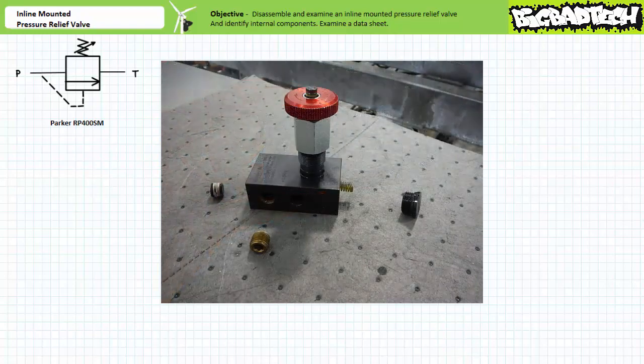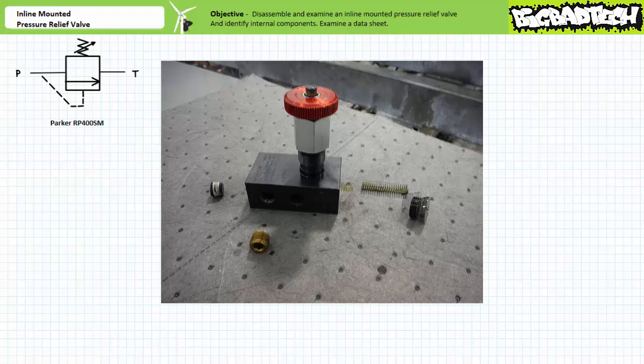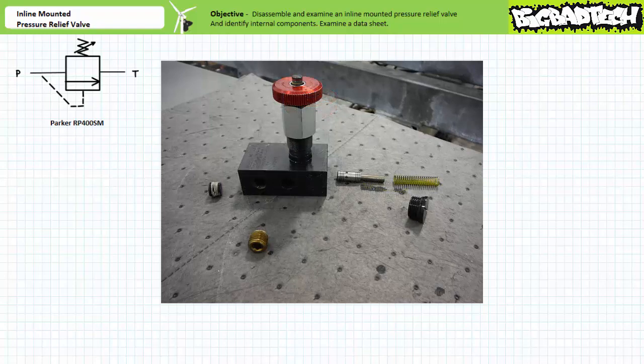We'll remove both the gauge and pressure plug and unscrew the end cap. Note the bias spring used to hold the primary piston closed, sticking out of the back. These are the springs that I was warning you about earlier. If forcibly ejected springs don't poke you in the eye, they will fly across the room and rattle down the nearest floor drain if you aren't prepared for them. Note the end cap has an O-ring around it. We can pull out the bias spring.